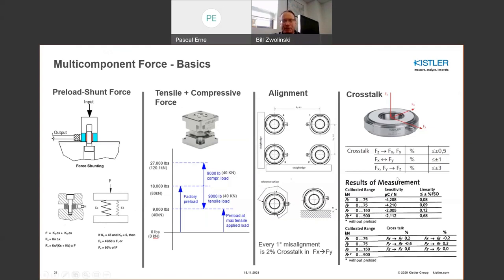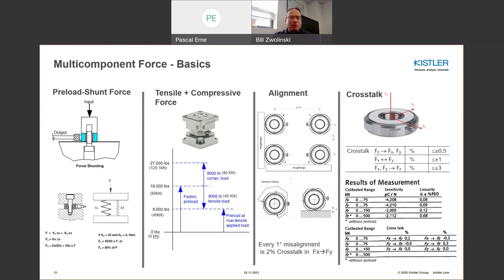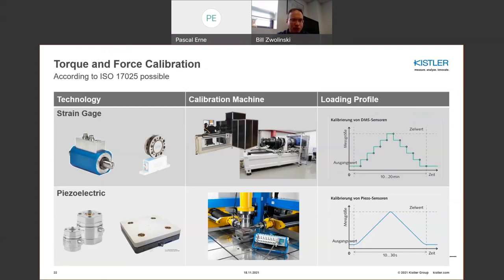In any installation of multi-component force sensors, always ensure alignment — every one degree of misalignment in X and Y could be 2% crosstalk between X and Y. Sensors are designed with flats on each side so they can be aligned with straight edges, making for a really high performance, low crosstalk solution. In a data sheet you might see crosstalk values upwards of 3% for how X and Y affect Z, but in calibration, crosstalk is generally less than 1% — in one example it was essentially 0% on the calibration certificate. Often the actual calibrated crosstalk is far better than general data sheet values. For torque and force calibration, strain gauge rotary torque sensors are calibrated piecewise while piezoelectrics are calibrated in a continuous fashion — both techniques are quite accurate, just requiring different methods.